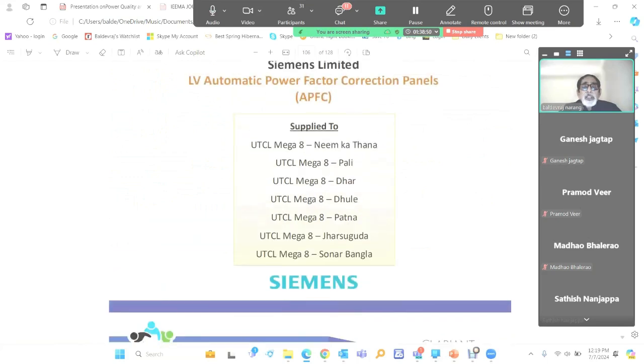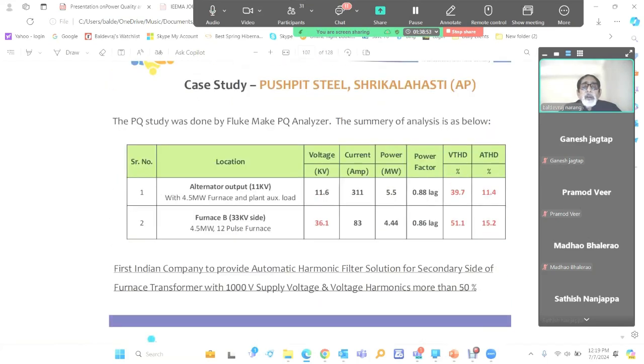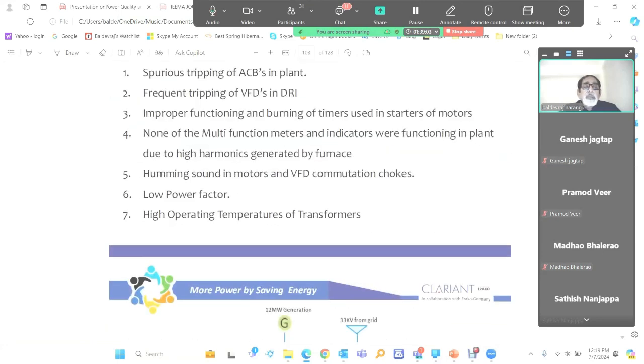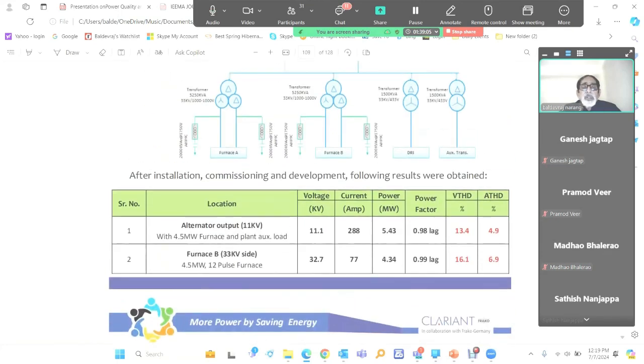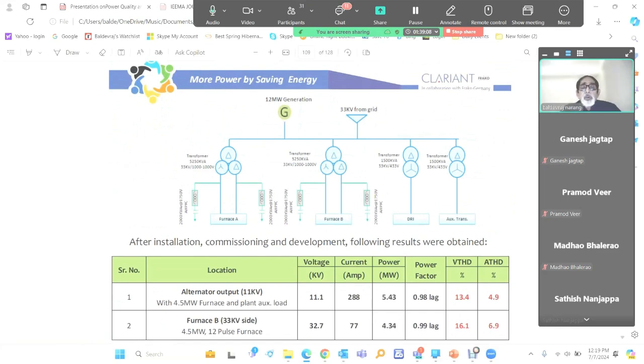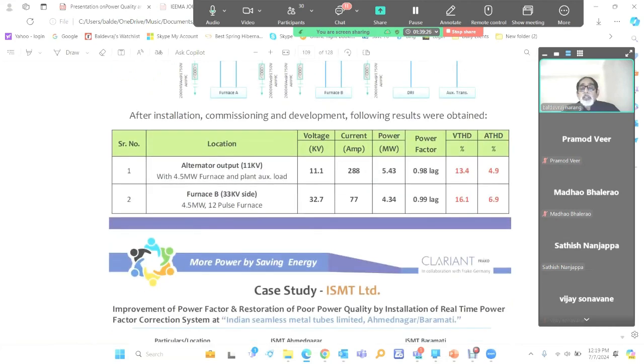And then some case studies are there. Their initial power factor we have shown, final power factor, how we have achieved it, how we have removed the harmonics. All these before and after readings are shown. This is again one steel factory where they were not able to run the plant on their own generation, though they could with the grid, because that is a very large system. It's like an ocean. They can run any amount of harmonics. But when they were on their own system, the generators were tripping. So there we gave the passive filters and we could reduce the harmonics.